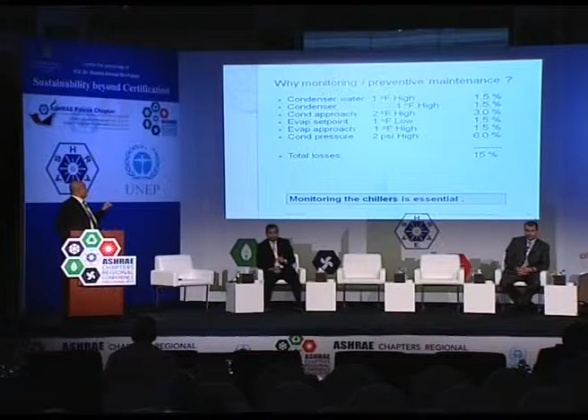One more important aspect in maintenance: if you have the most efficient chiller plant and you don't maintain it properly, your approach will be higher, on both evaporator and condenser. Your refrigerant might be a little bit less than expected. You can lose up to 15% on your design condition.